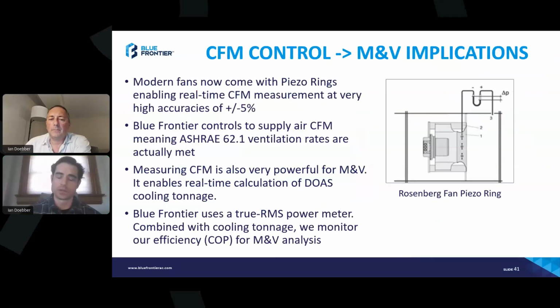Then switching over to ventilation, this is an element that's not unique to our system. A lot of you have seen this evolution in the fan world: more sophisticated direct drive ECM fan motor systems are coming with what's called a piezo ring. Essentially, this measures the static pressure between the suction of the fan and the inlet nozzle. This is a nozzle flow measurement, which is very accurate. Our fans use this, so we're actually controlling our fans to CFM.